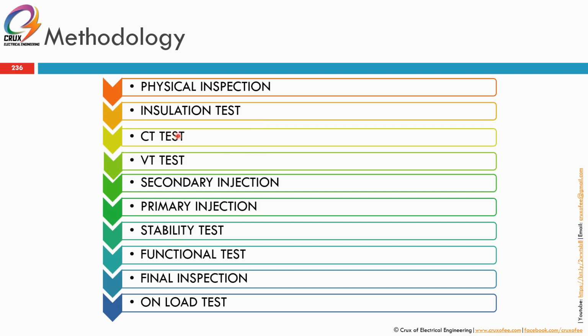And then we will have a CT test to test the CT, a VT test, secondary injection, primary injection, then a stability test to check the differential relay, and also to check whether your CT is correctly arranged in terms of its polarity, and a functional test. This functional test is mainly for the switchgear and the motor and so on. And the final inspection, and finally, once energized, is the on-load test. Okay, the final inspection is before energization.